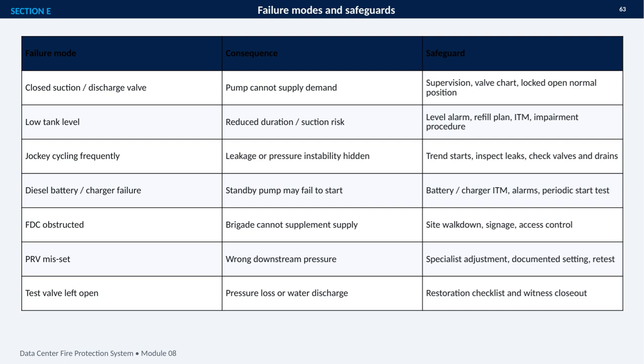A closed suction or discharge valve can prevent the pump from meeting demand, so valves need supervision, clear valve charts, and a locked-open normal position. Low tank level creates both reduced water duration and suction risk. That calls for level alarms, a refill plan, inspection, testing, and maintenance, or ITM, along with an impairment procedure. Frequent jockey pump cycling can indicate leakage or pressure instability, so trend starts and inspect leaks, check valves, and drains.